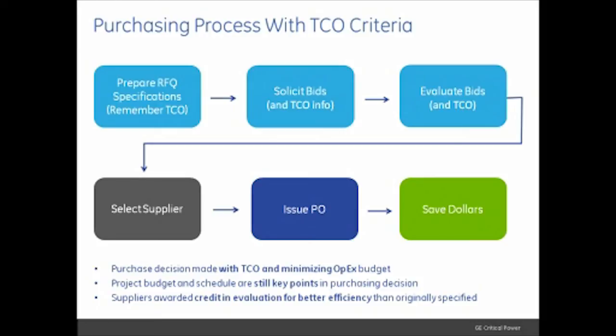Some of the pieces of information they ask for may include the efficiency at the designed operating point of the UPS. For instance, in a system plus system, that may be somewhere around 40 to 45%, or it might be lower, at 30%. In an N+1, it might be 60 or 65% of UPS capacity. So knowing exactly what the efficiency is at the load point is a key factor.